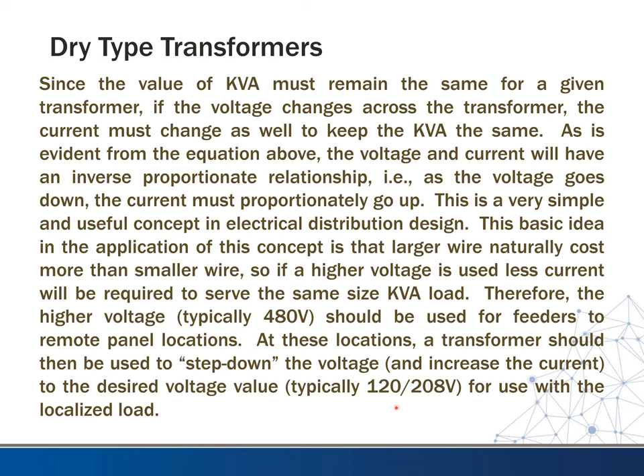The basic idea and the application of this concept is that larger wire naturally costs more than smaller wire. So if a higher voltage is used, less current will be required to serve the same size KVA load. Therefore, the higher voltage, typically 480, should be used for feeders to remote panel locations. At these locations, a transformer should then be used to step down the voltage, in a sense, and increase the current to the desired voltage value, typically 120/208, for use with the localized load. So this saves us some wire size and feeder size until we get to our 120/208 panel need or location.